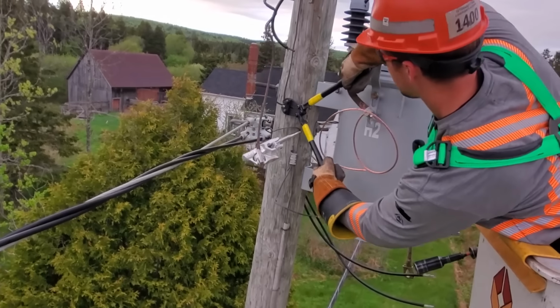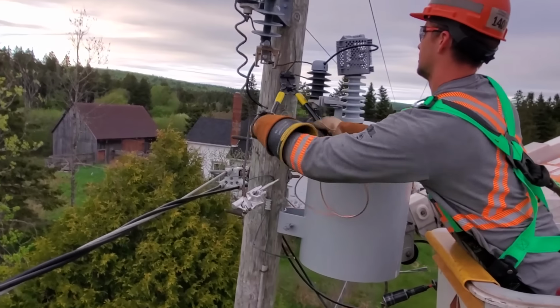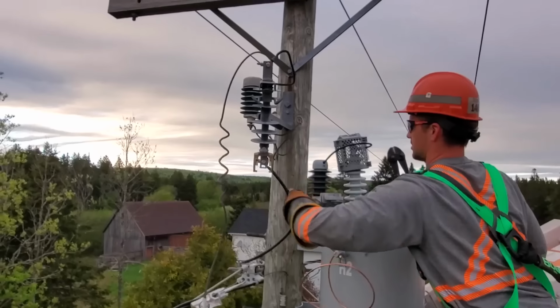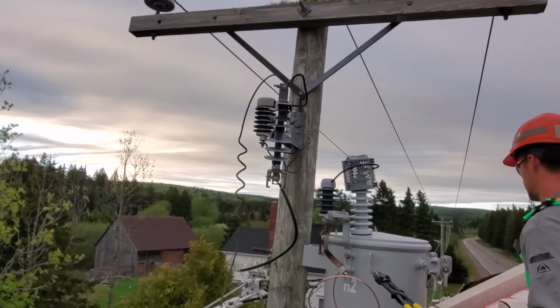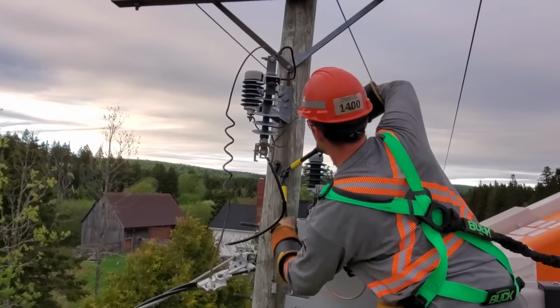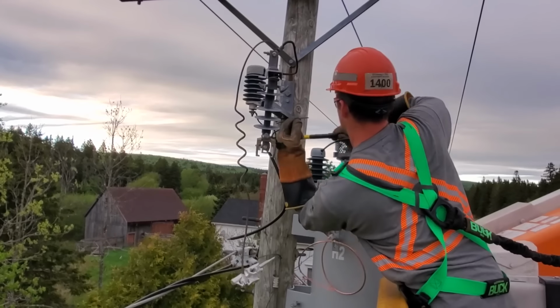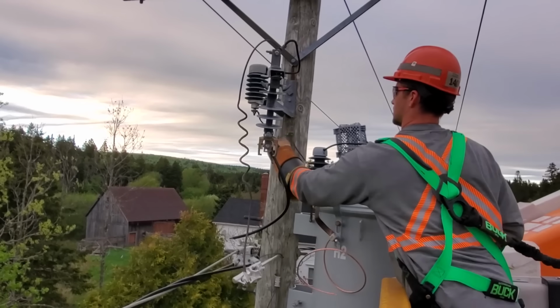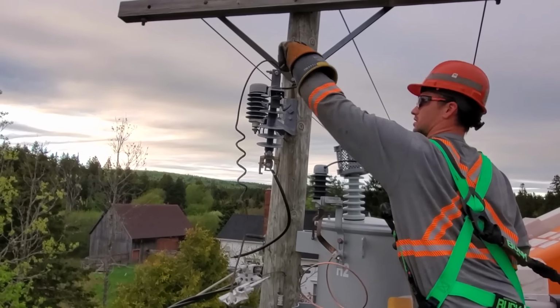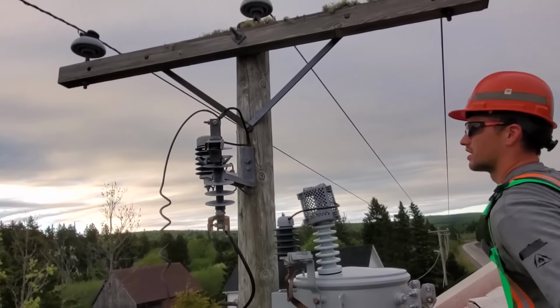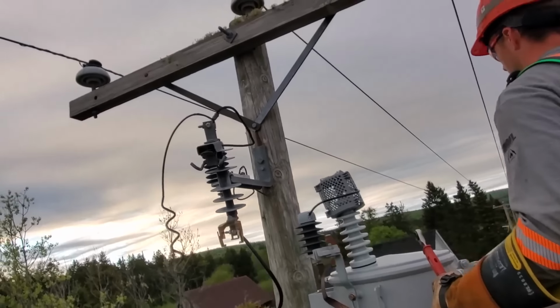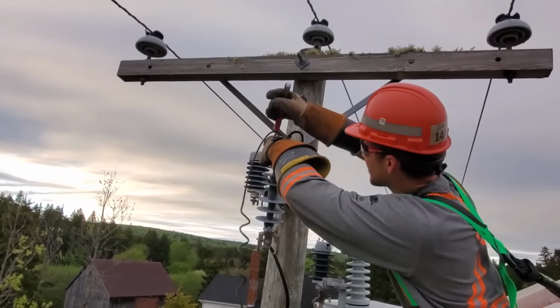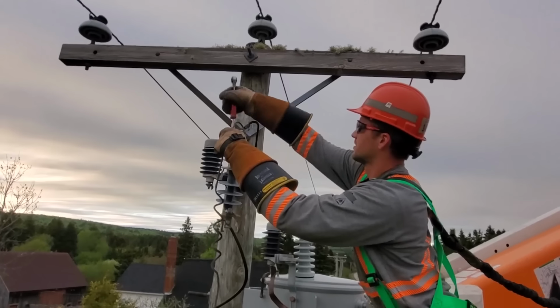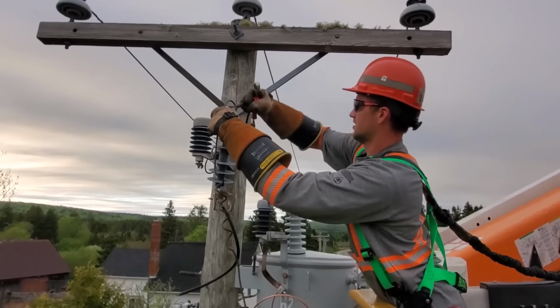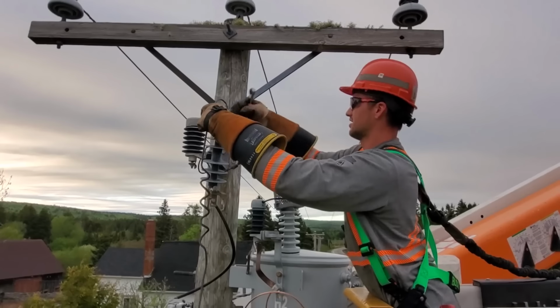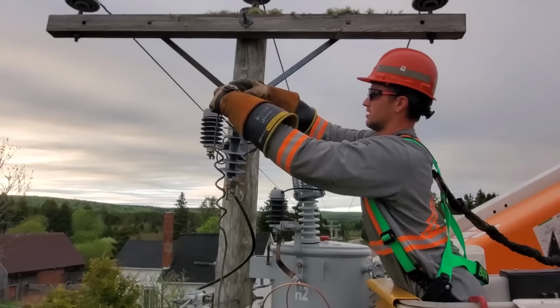So he's just cutting that lightning arrestor clear there now. Absolutely no point in having two lightning arrestors on the pole. It just creates a hazard. And that looks like it's crimped onto that lead, so he might have to cut that off. You'll notice that Ryan was just looking up at the primary. It's very important whenever you're working on a pole, especially when you're this close to the primary, that you constantly check your position on the pole, check how close you are to any live leads. Always be aware of your position on the pole.